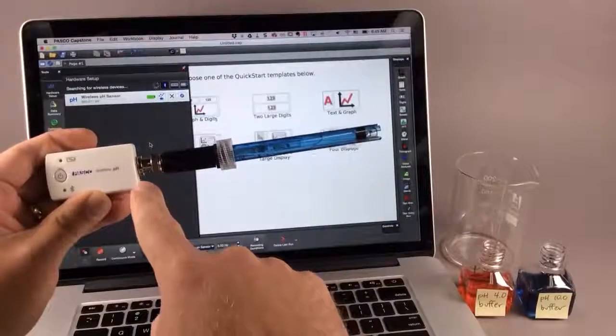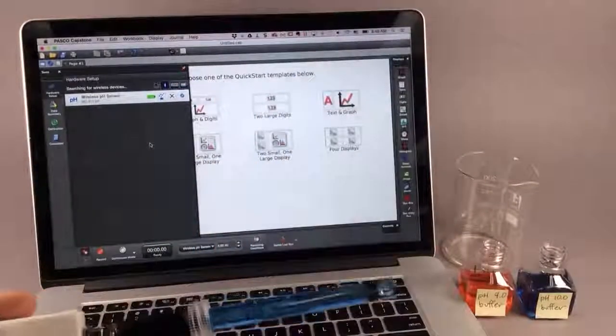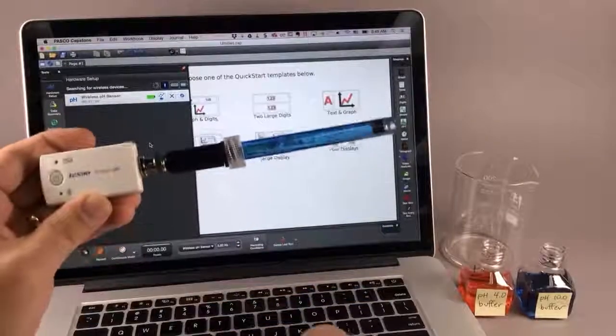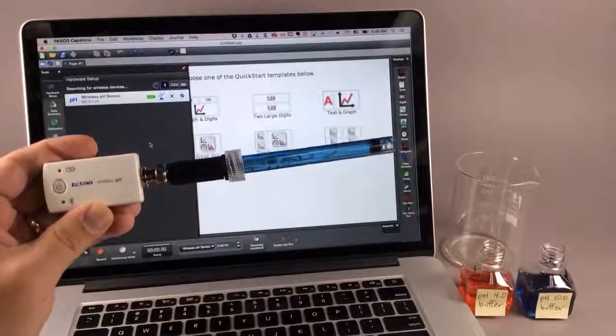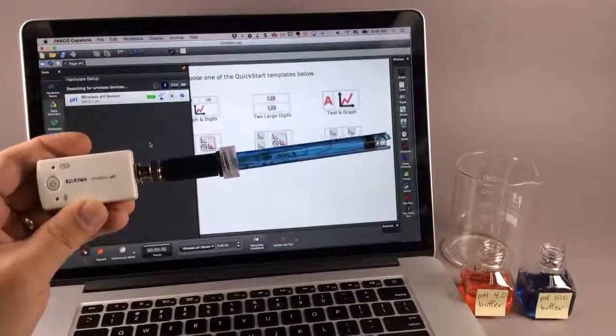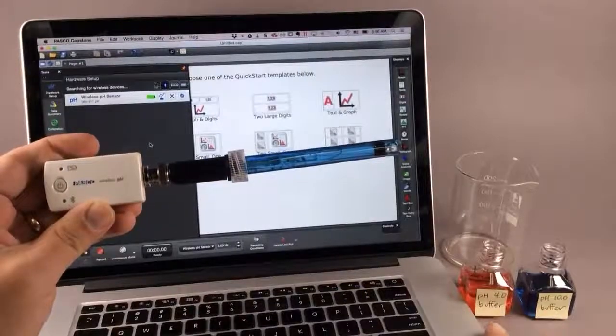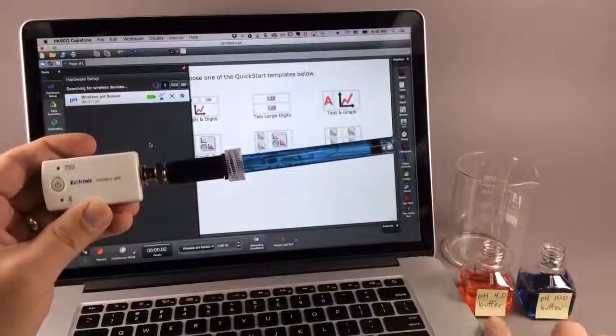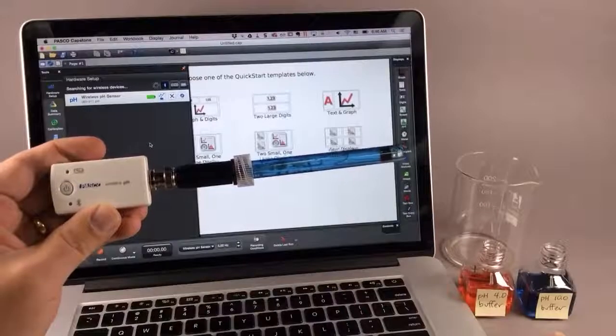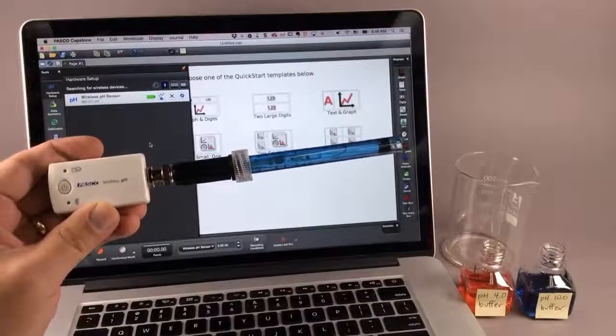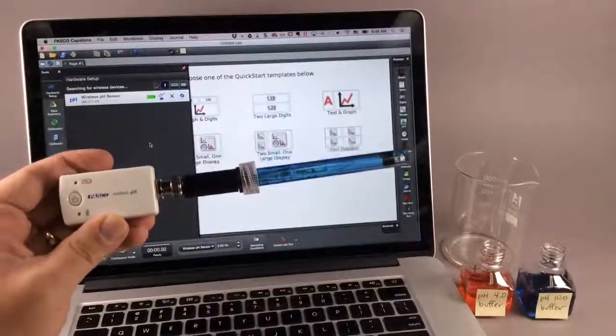How do I calibrate the wireless pH sensor using PASCO Capstone software? If you want to improve the accuracy of your pH measurements, you can calibrate the wireless pH sensor in the software using a pair of solutions of known pH. In this example, I have pH 4 buffer and pH 10 buffer. I also need a rinse bottle, a tissue, and a place for the rinse water.